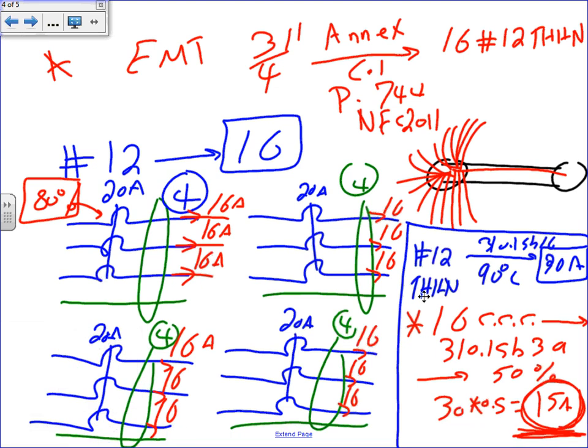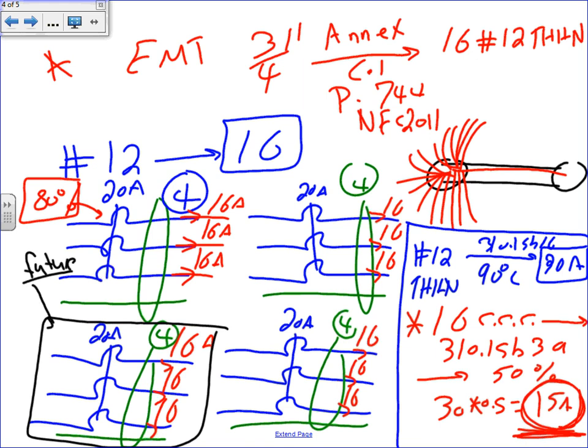Okay, let me, as of now, go circuit by circuit. I want to write a disclaimer here. What I usually do, guys, is take one of these circuits. A lot of people take one of these circuits and make a few turns, meaning when I load my pipe, I load it with 12 conductors instead of 16 conductors. Why? For future expansion, I'm allowing them to stick another 4 conductors to go somewhere else. It's an idea. Here's one way of doing it.